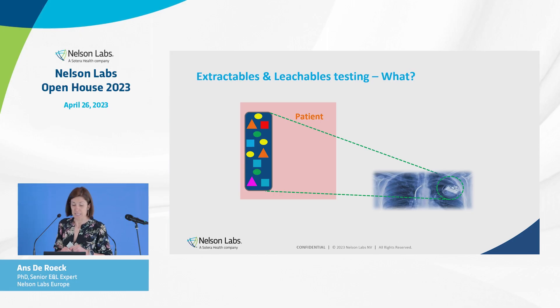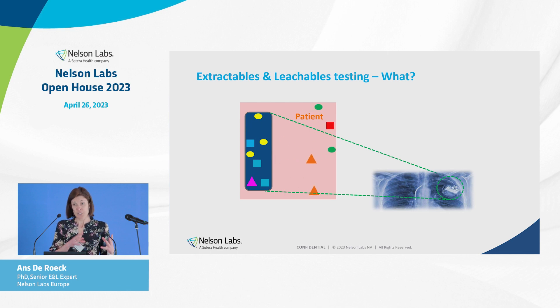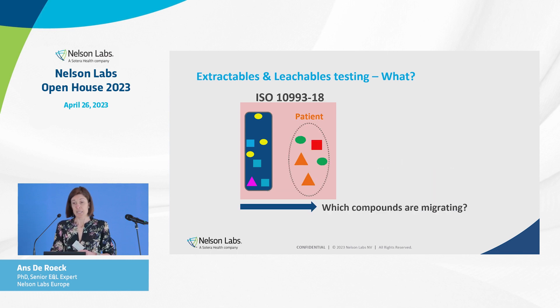So what is extractables and leachables testing? Here we have the example of a pacemaker implanted in a patient. On this device there can be compounds still present from the manufacturing process, the packaging, or the sterilization process. These compounds might leach into the patient and cause health issues. In E&L testing we are interested in which compounds can migrate from the device into the patient and at which concentrations. This is described in ISO 10993 Part 18.